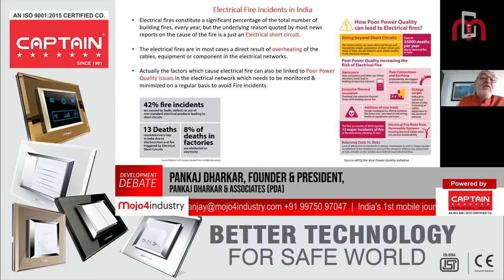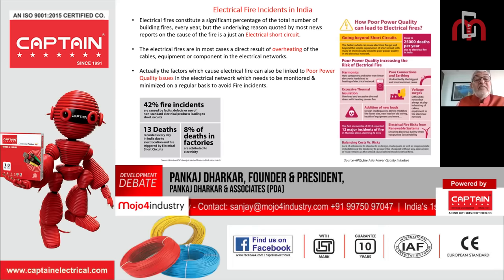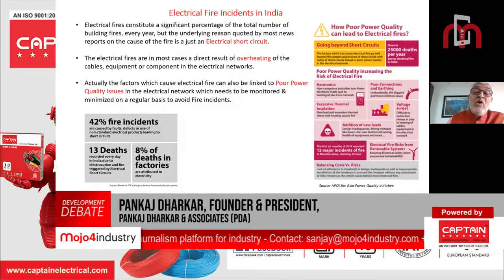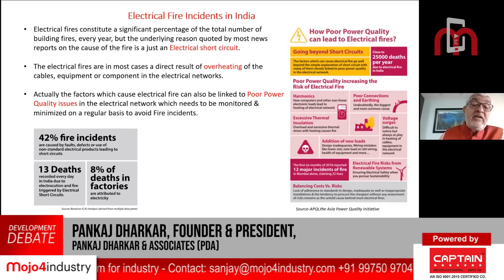Electrical fire constitutes a significant percent of total building fires every year, but the reason quoted by most news reports is just an electrical short circuit. Electrical fires are in most cases a direct result of overheating of cables, equipment, or components in electrical networks. The factors causing electrical fire can also be linked to poor power quality issues in the network, which need to be monitored and minimized regularly to avoid fires.